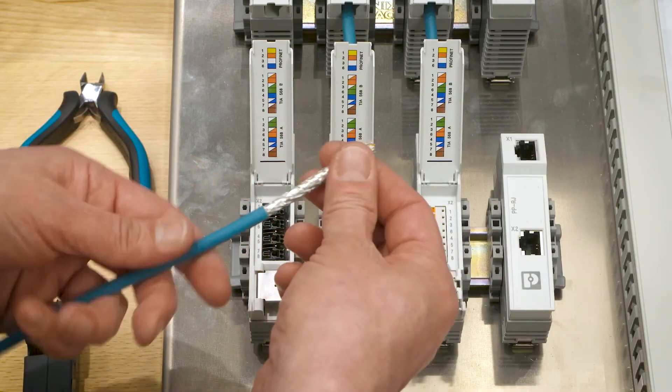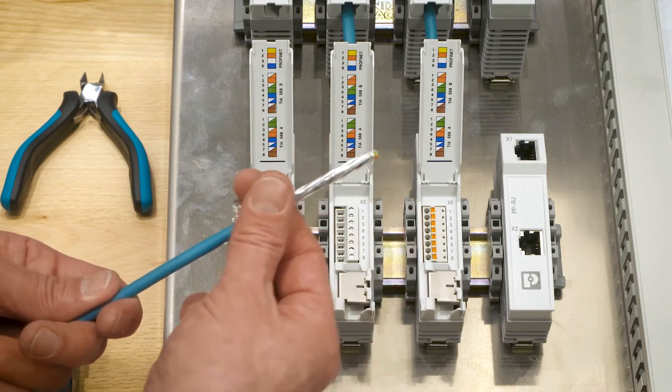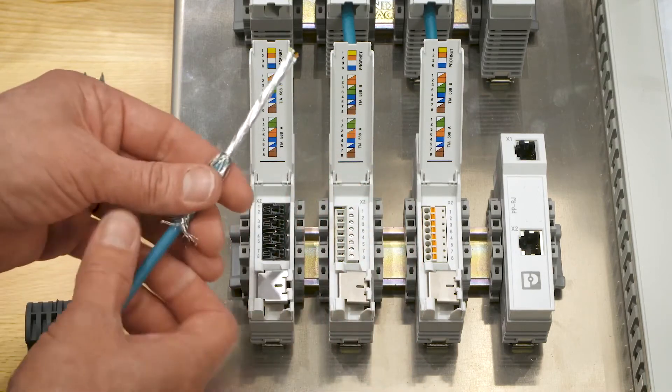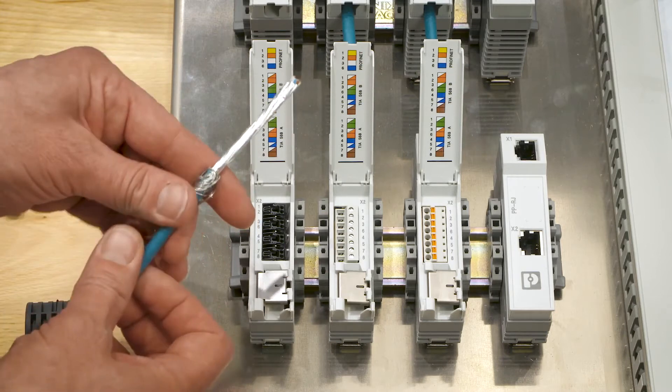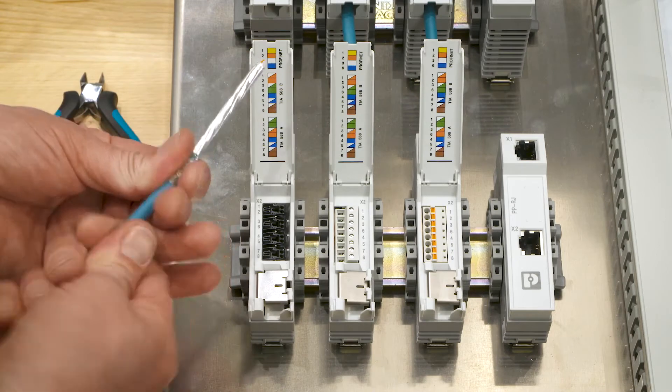The sheath is removed and the braided shield is folded backwards. And to achieve a large grounding or contact surface, I'm wrapping it around the cable sheath. I must now prepare these four pairs.